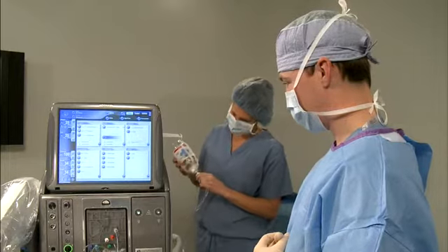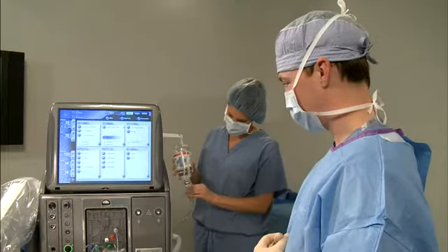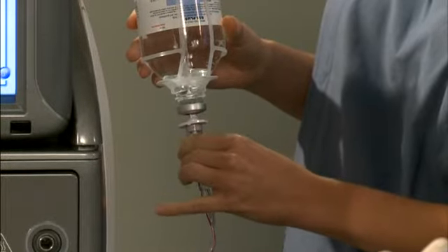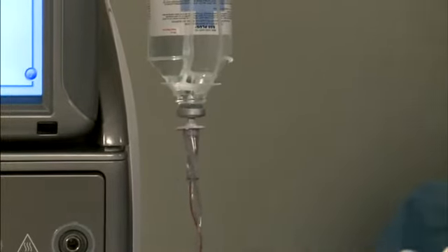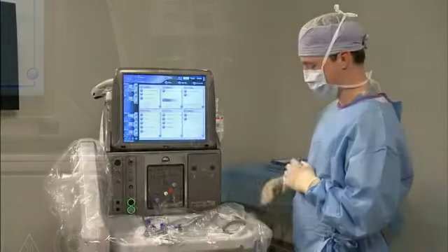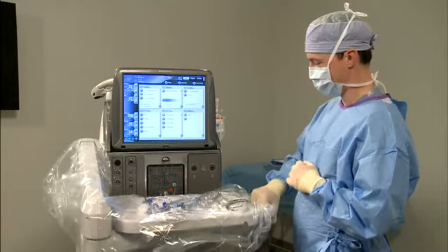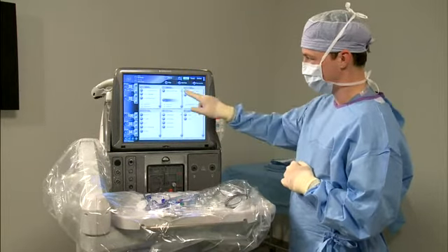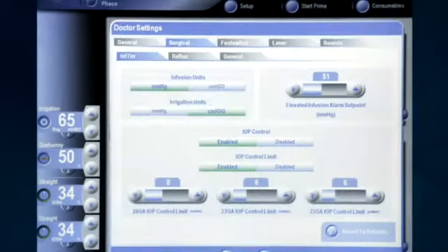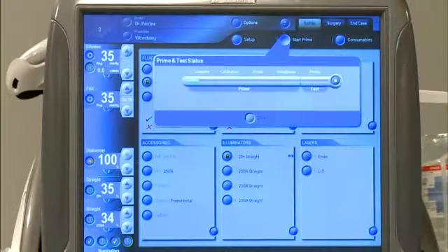Remove the protective cover from the drip chamber and aseptically spike the irrigation bottle. Squeeze the drip chamber to fill approximately 2/3 full. Before priming is initiated, ensure that the tray arm is at mid-cassette level and that IOP compensation is enabled. Press the Start Prime button on the touchscreen to initiate priming. The process may take 1 to 2 minutes, and care should be taken not to bump the tray arm or disturb the handpieces during priming and tuning, as this may affect calibration.